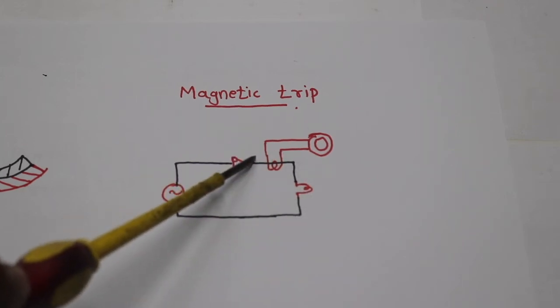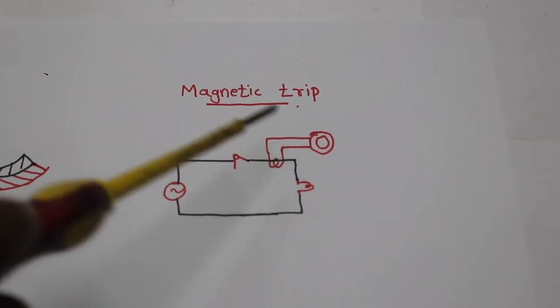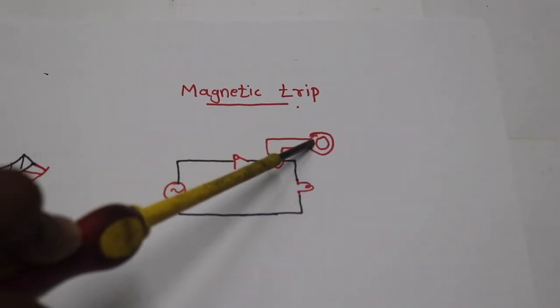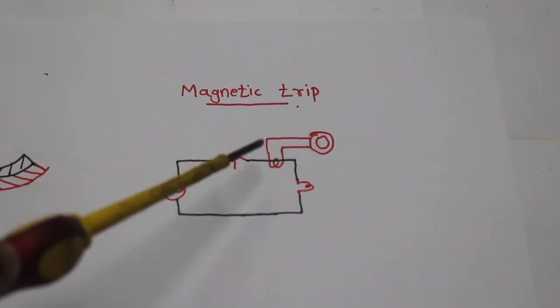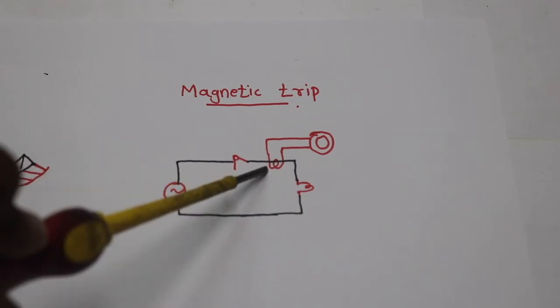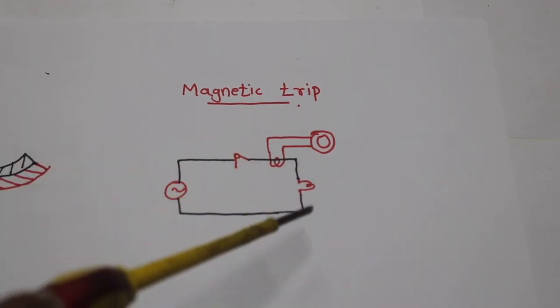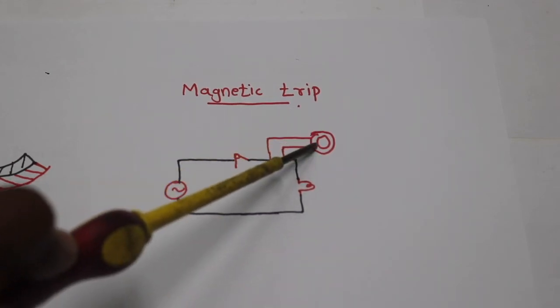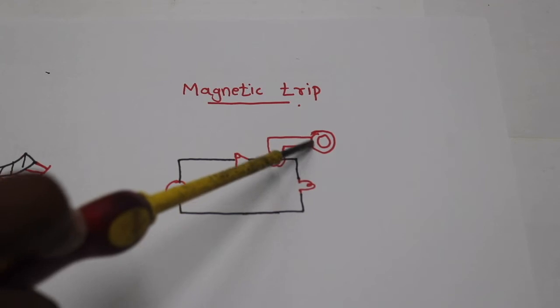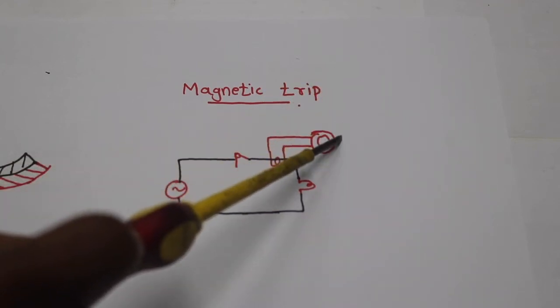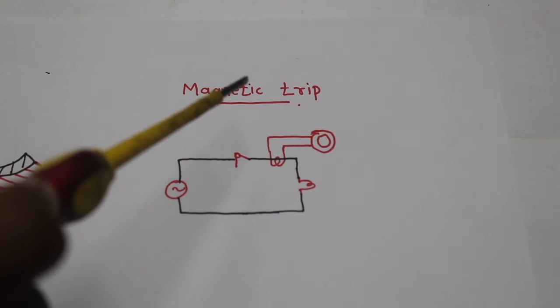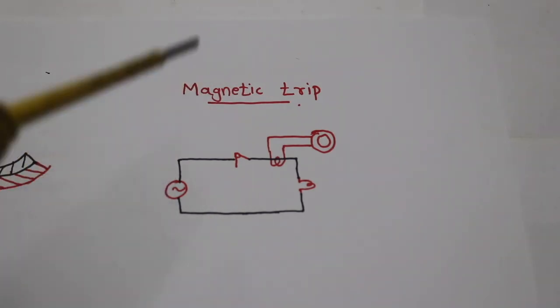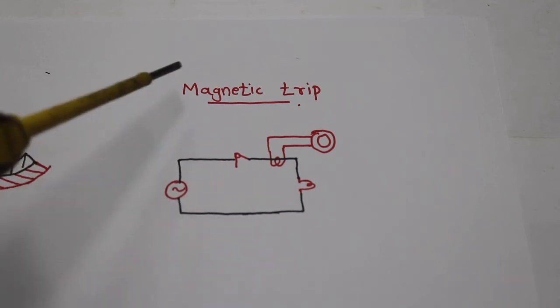Now we have a load. In this case, current flows into the metal. When it comes to an overcurrent, it flows as a large current. When this large current flows, it acts as a magnet and attracts the other metal. This is the mechanism that makes the MCCB trip. This is short-circuit protection — the magnetic trip.